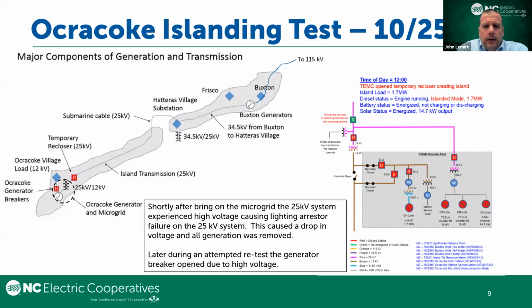The diesel is the grid forming entity, meaning that in the outage the diesel starts first to form the island, and then the battery and the solar are used to supplement that generation. When we tested our use case and we brought the system back online, we were told that the 25 kV system experienced very high voltages, causing lightning arresters to fail, dropping out the voltage and kicking the generator offline. When we attempted to re-sync and perform the test again, we had the assets trip off.